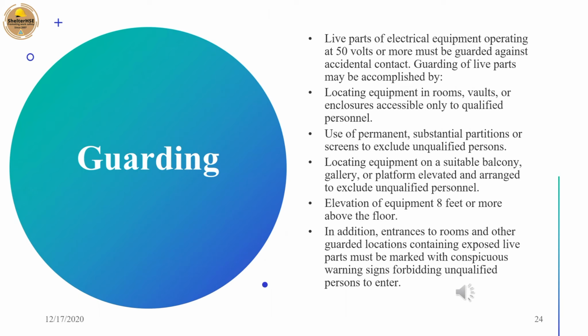Live parts of electrical equipment operating at 50 volts or more must be guarded against accidental contact. Guarding of live parts may be accomplished by locating equipment in rooms, vaults, or enclosures accessible only to qualified personnel. Use of permanent, substantial partitions or screens to exclude unqualified persons. Locating equipment on a suitable balcony, gallery, or platform elevated and arranged to exclude unqualified personnel. Elevation of equipment 8 feet or more above the floor. In addition, entrances to rooms and other guarded locations containing exposed live parts must be marked with conspicuous warning signs forbidding unqualified persons to enter.